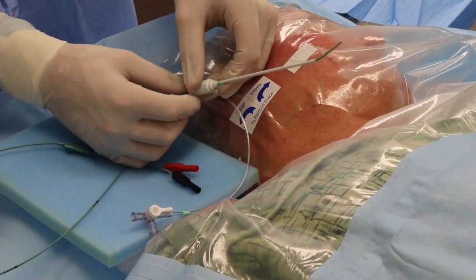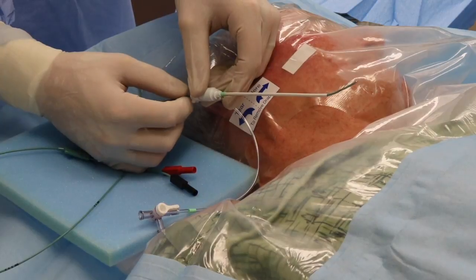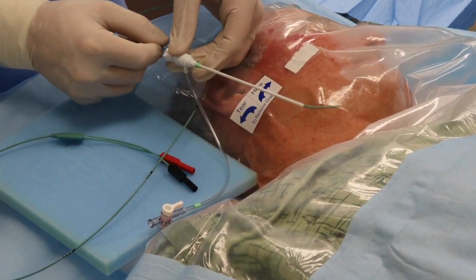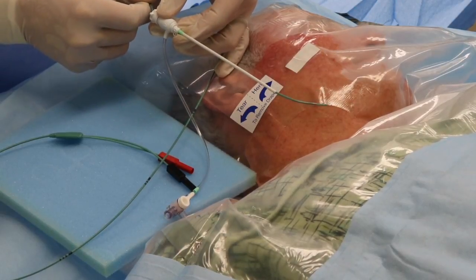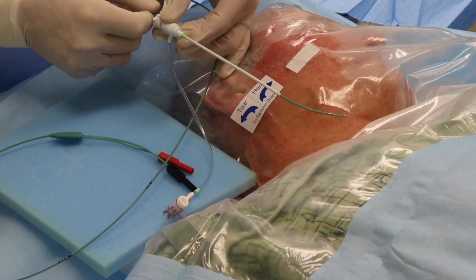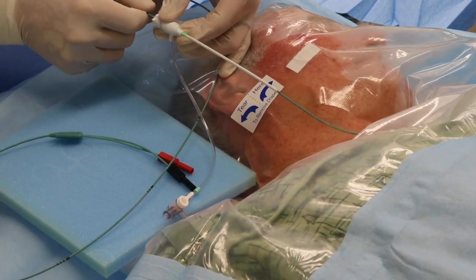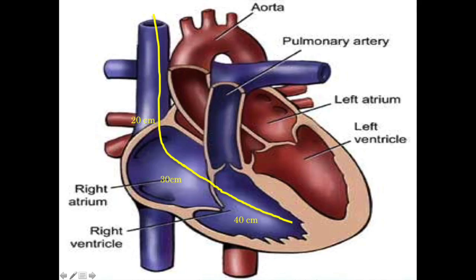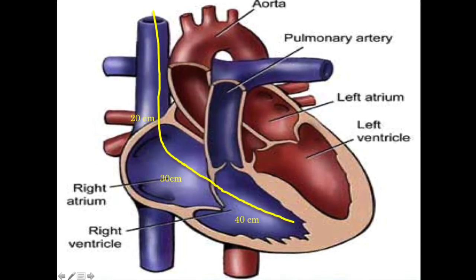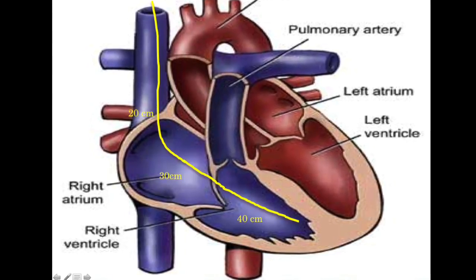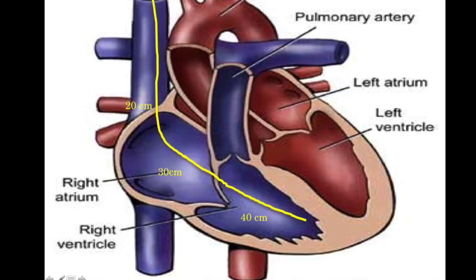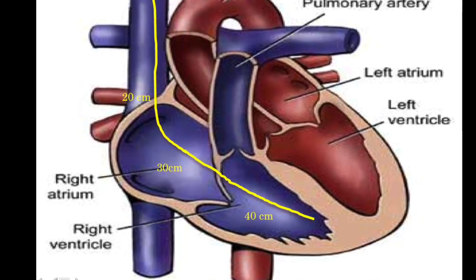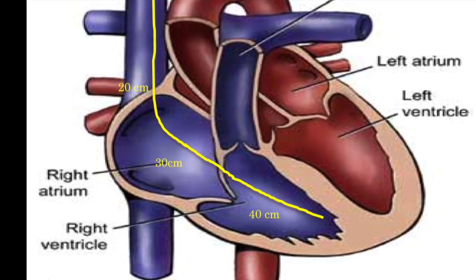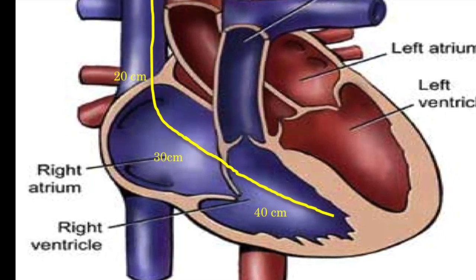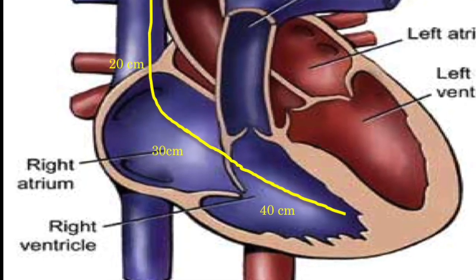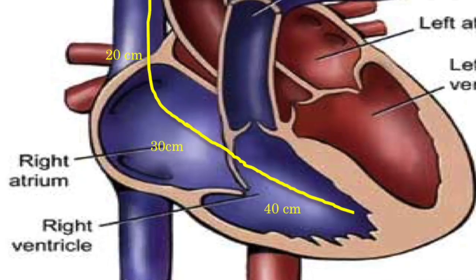Now we don't have a Swan-Ganz balloon catheter yet, so it's important that you put the memory of the wire facing the atrioventricular valve as it goes through the valve into the right ventricle. It'll just kind of guide its way through. As you can see by this diagram, at 20 centimeters it's just above the right atrium. At 30 centimeters you're pretty much in the atrium. At 40 and 50 you should be in the ventricle by now, and if you're not getting capture, that means you bypassed the right ventricle completely and you're actually in the inferior vena cava. By this time you'll probably see their diaphragm twitching and their body twitching if you have the pacer on.